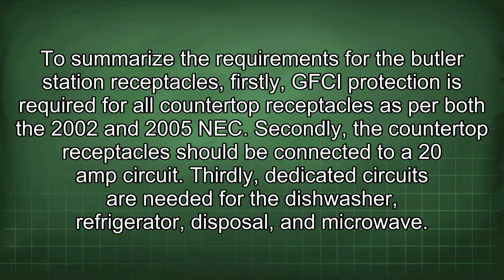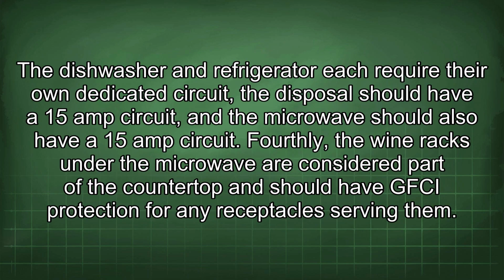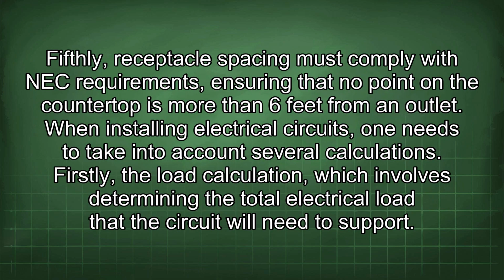Secondly, the countertop receptacle should be connected to a 20 amp circuit. Thirdly, dedicated circuits are needed for the dishwasher, refrigerator, disposal, and microwave. The dishwasher and refrigerator each require their own dedicated circuit. The disposal should have a 15 amp circuit, and the microwave should also have a 15 amp circuit. Fourthly, the wine racks under the microwave are considered part of the countertop and should have GFCI protection for any receptacles serving them. Fifthly, receptacle spacing must comply with NEC requirements, ensuring that no point on the countertop is more than 6 feet from an outlet.